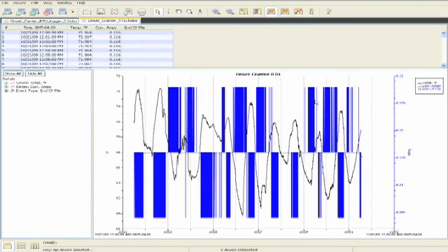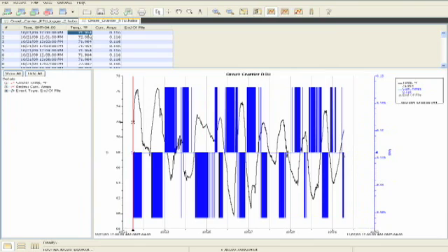And this graph here is showing in the black our temperature readings, and in the blue our amperage readings off our unit compressor. So we can see that the logging started on 10/21 at noontime with a temperature of about 72 degrees. And 0 amps on the compressor based on the fact it was not running right away.